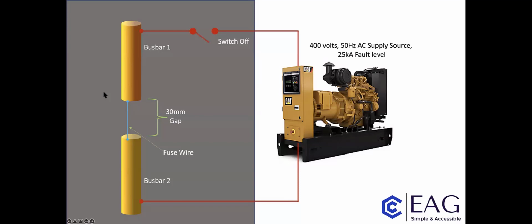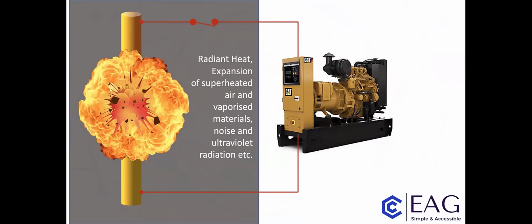When I ask electrical workers what will happen when the switch is closed, they often say that a large amount of current will flow and then the fuse wire will simply rupture or blow and rapidly disconnect the circuit. Well, actually what happens is that the fuse wire will vaporize, it'll melt, but in doing so will ionize the air between the two conductors and create a low impedance path.